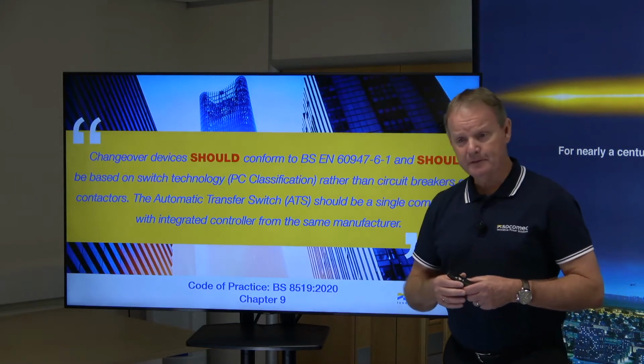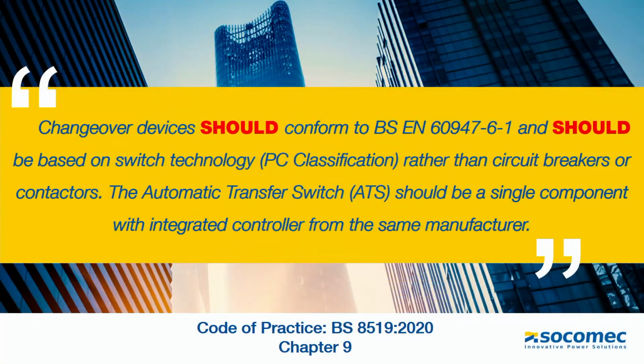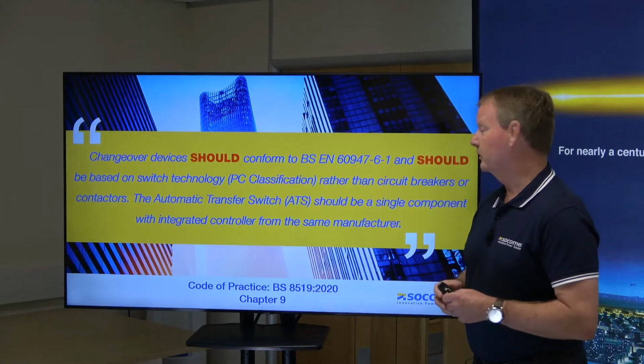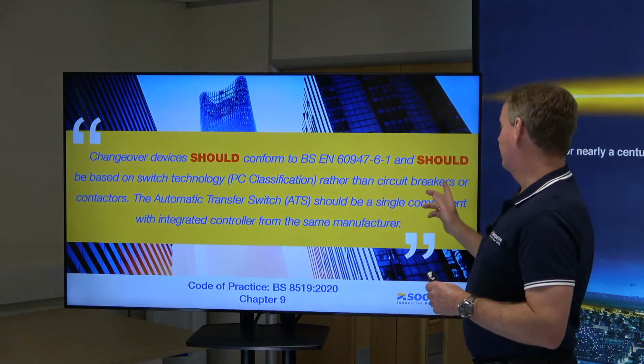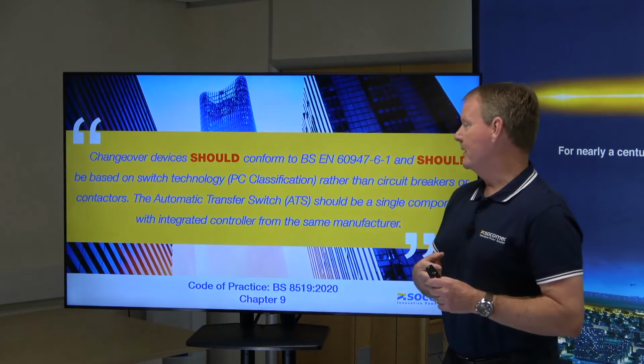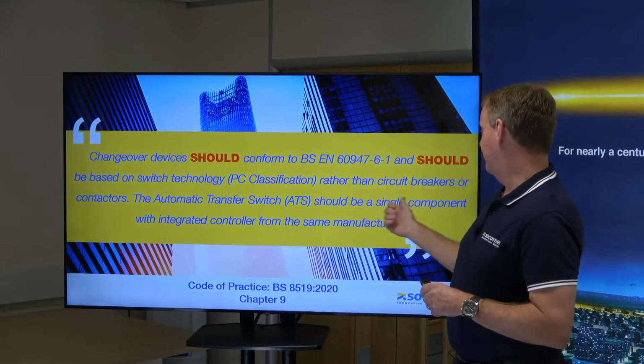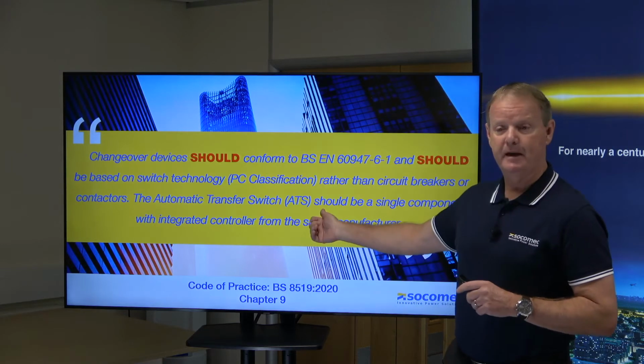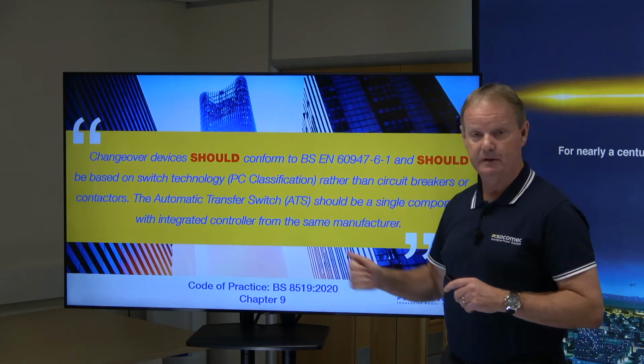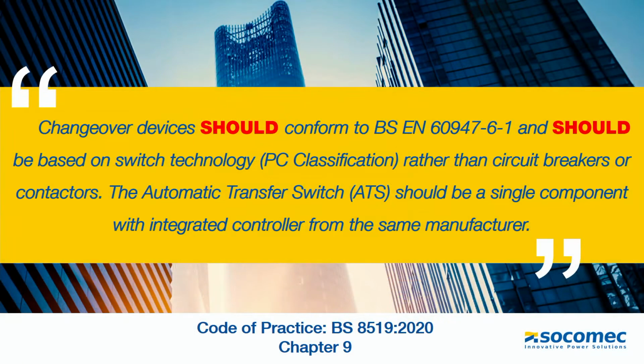As we said before, the major change now is that changeover devices should, which means must, conform to BS EN or IEC 60947-6-1, which is a product standard, and should be based on switch technology, PC classification, which we'll show you a bit later, rather than circuit breakers or contactors. So the automatic transfer switch, or ATS, should be a single component with an integrated controller from the same manufacturer. There's a key point there which we'll demonstrate a little bit later on. And this is a code of practice, under Chapter 9.